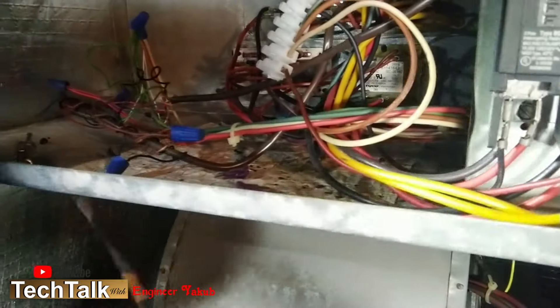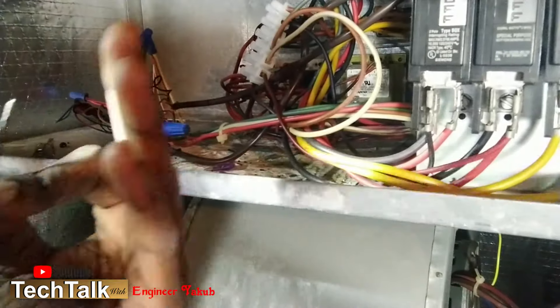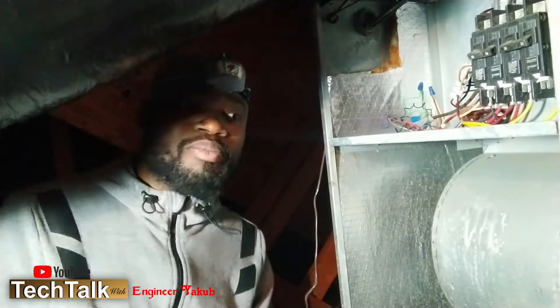From the burnt cable, I cut off the already burnt part to get a good section of cable, stripped it and cleaned it up. The technician had already removed my capacitor. I normally allow professionals to do their job — I've called these guys to the house several times for other issues. But the amount the guy quoted me was just outrageous, and that's really what kicked off this DIY decision. I'm about to fire this up and see if it works.